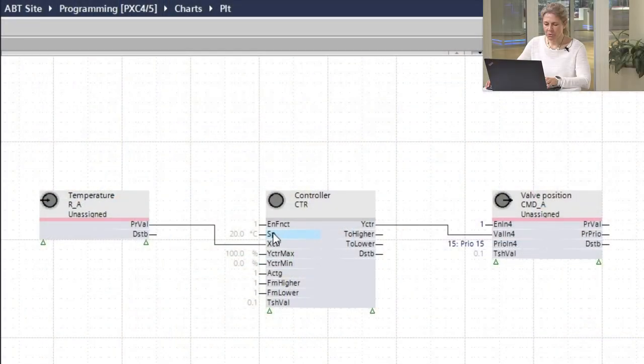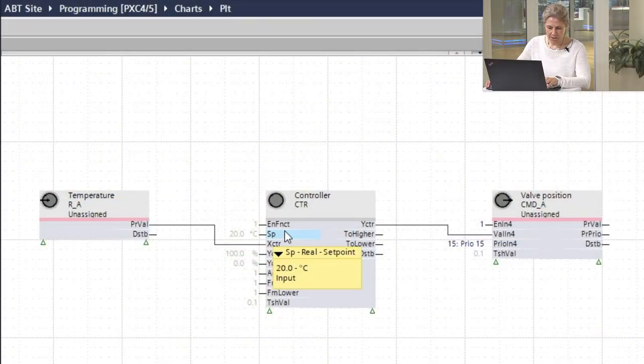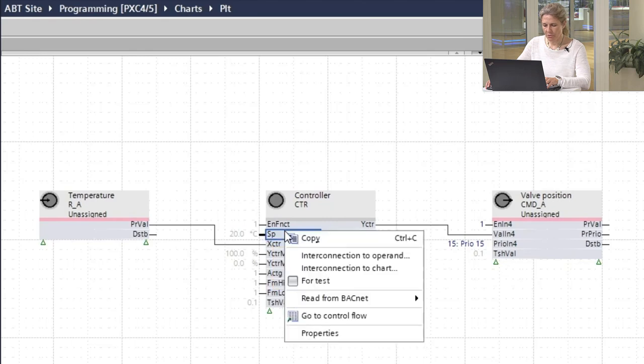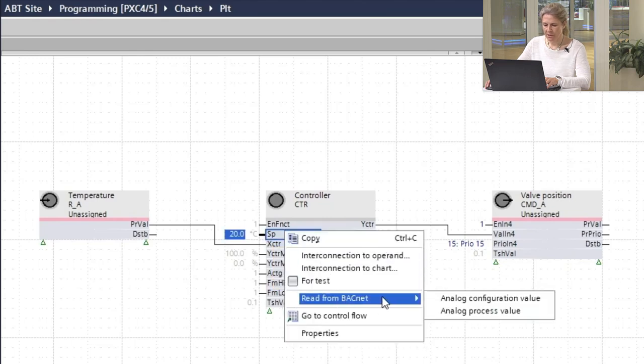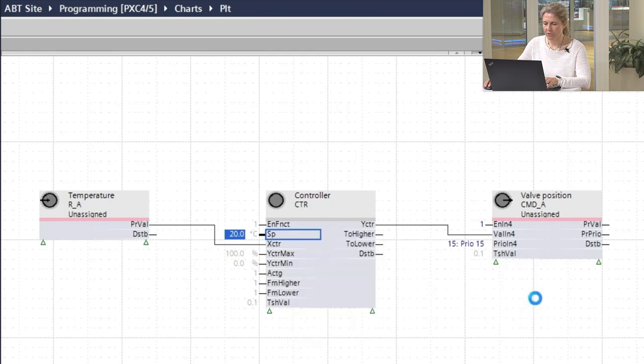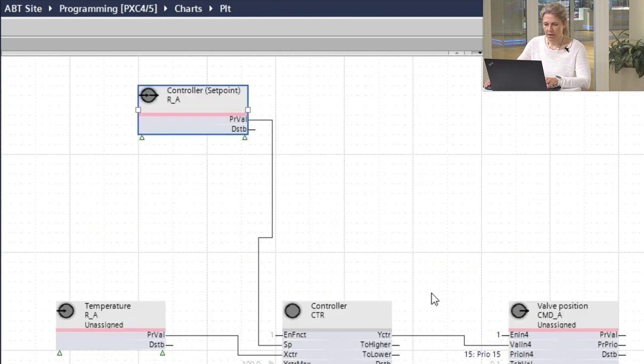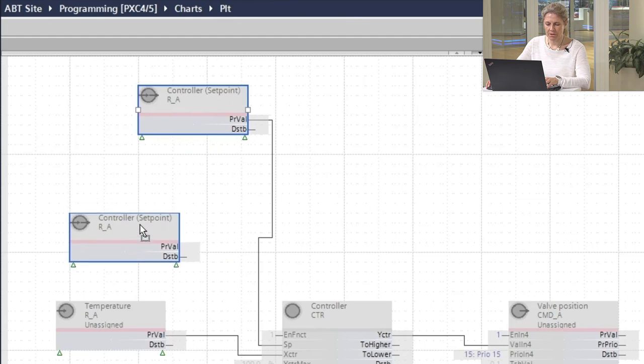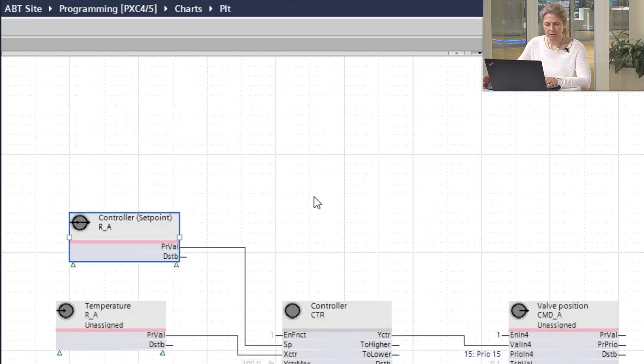For this, all you have to do is go to the set point pin of this controller, right click and choose read this information from BACnet as an analog configuration value object. Click and here you have your set point available in the program.